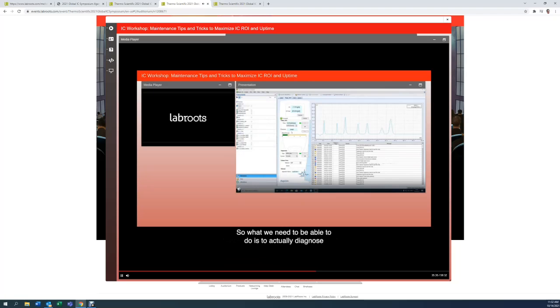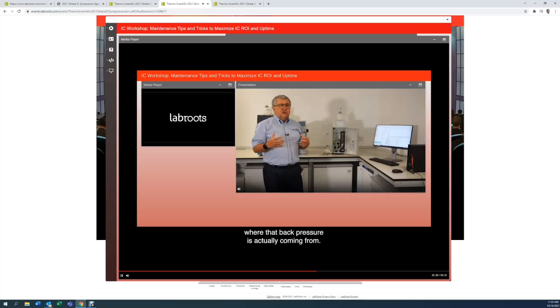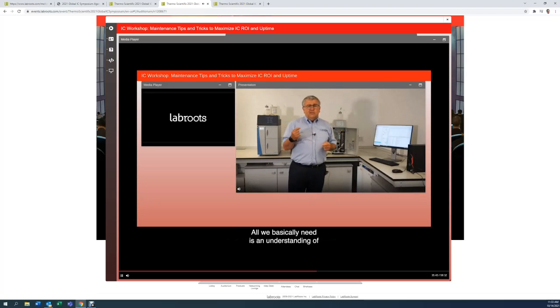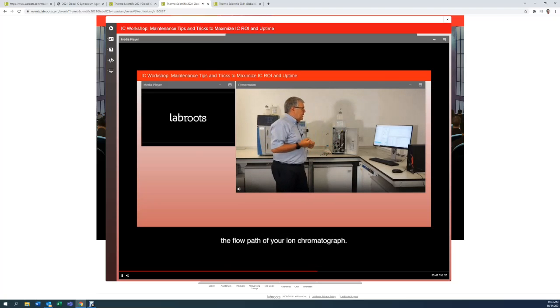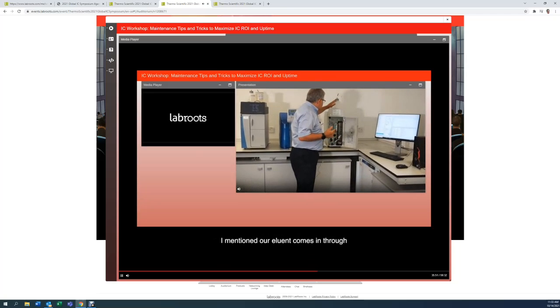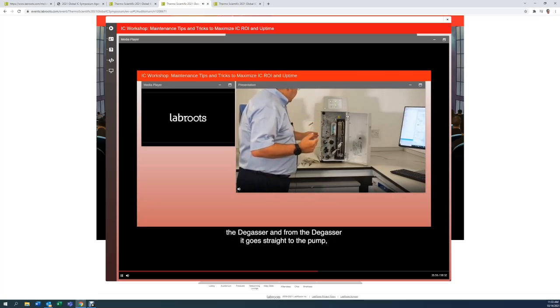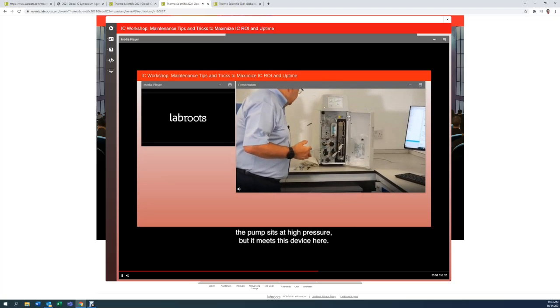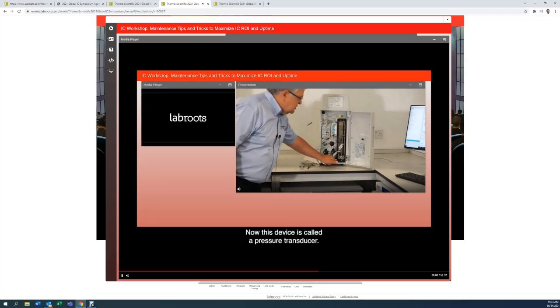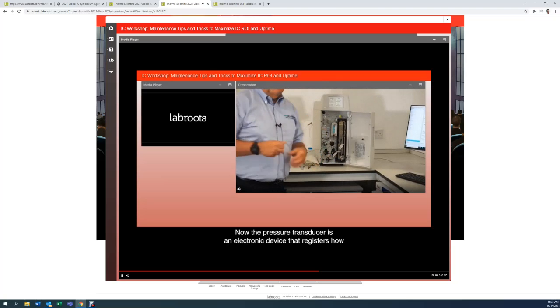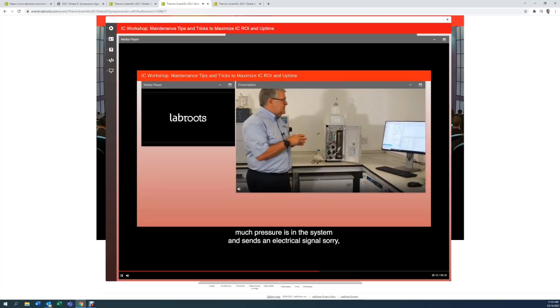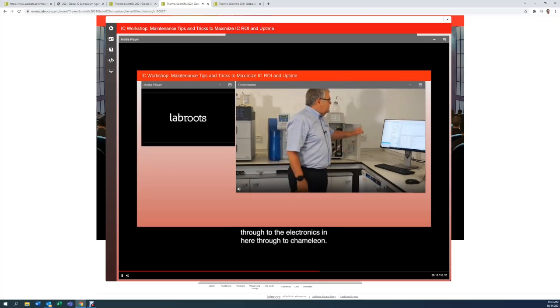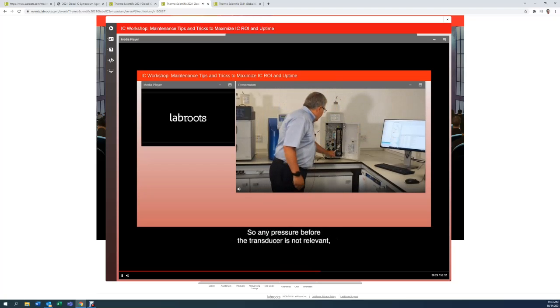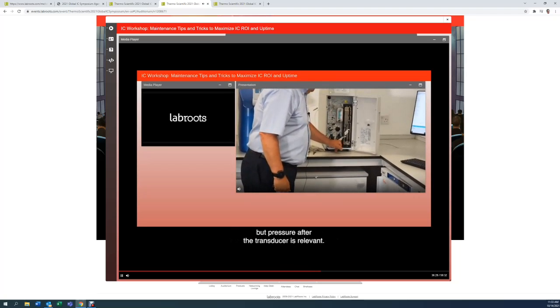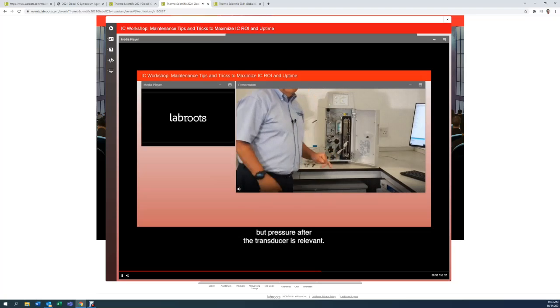We need to diagnose where that back pressure is coming from, and we can do that very simply. All we need is an understanding of the flow path of your ion chromatograph. As I talked about yesterday, the eluent comes in through the degasser and goes straight to the pump. The pump pumps it at high pressure, but it meets this device, the pressure transducer. The pressure transducer is an electronic device that registers how much pressure is in the system and sends an electrical signal through the electronics to Chameleon, and that's where that number is read out, 2,493. So any pressure before the transducer is not relevant, but pressure after the transducer is relevant.